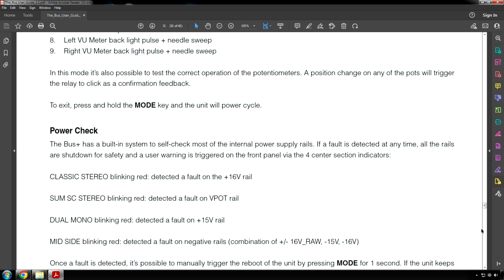Power check. The Bus Plus has a built-in system to self-check most of the internal power supply rails. If a fault is detected at any time, all the rails are shut down for safety and a user warning is triggered on the front panel via the 4 center section indicators.